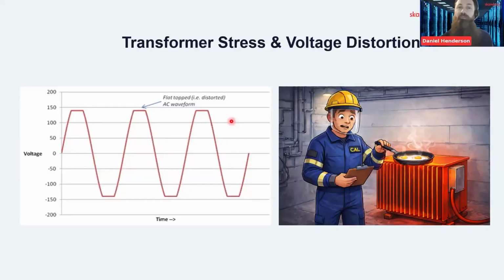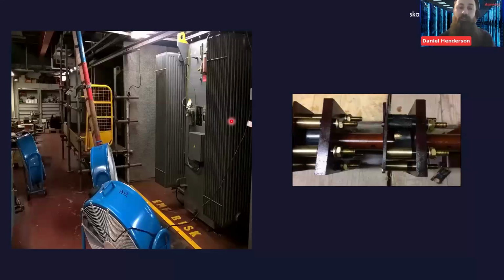But essentially, I saw that manifesting again, starting to get faults back at the tap changer, and seeing that oil start to degrade. And one of the worst ones, the one that kept me awake at night, was this example. This was a transformer that fed part of a process. Again, on the tally plate and on the size of the variable frequency drive that it fed, it was more than capable of supplying that load, but taking into account that FHL of 7 on this one, essentially, this was catastrophically failing around every 10 years. When I look back through the history records, and I'm talking catastrophic failure. So it was a failure of the tap changer, hot oil, flashover, and you don't want to be in the vicinity of that when that fails.